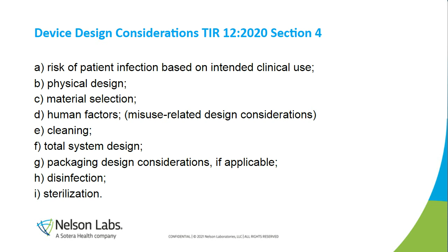All right, we are going to begin with Device Design Consideration A, risk of infection based off of clinical use. And before we discuss the risk of infection, we're going to skip ahead in the document to Annex F. Table F1 is a new addition to TIR12 and shows relative resistance to sterilization and disinfection of microorganisms. At the bottom of the table, you can see microorganisms such as lipid envelope viruses that pose the least challenge to inactivation by sterilization and disinfection. And I use inactivation because viruses are not alive and can't be killed.